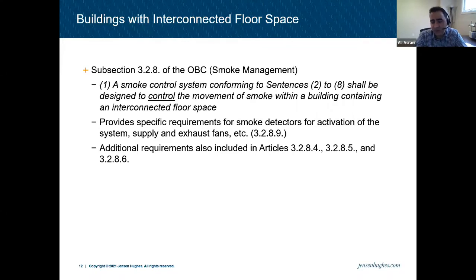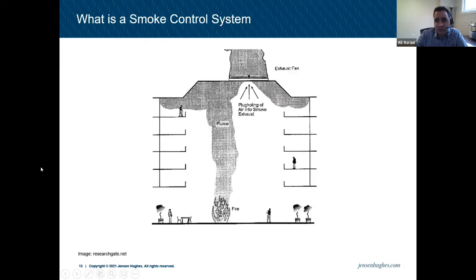It's asking for specific smoke detectors at certain areas, dampers and supply fans here and there. There are additional requirements under 3.2.8.4, 5, and 6. This is not necessarily a high building, and as soon as you have this interconnected floor space that does not meet one of the exceptions in the building code, you have to have this smoke control system.